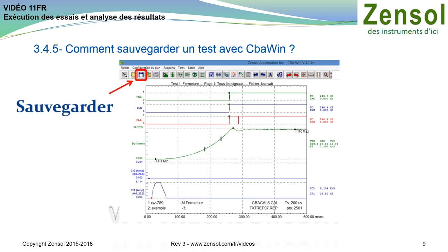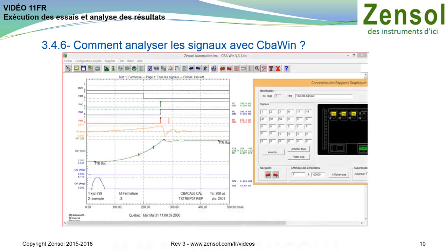As mentioned above, the red buttons are used to analyze the various signals. To zoom in on the curves, use horizontal and vertical expansion. To zoom in on the calculations on the right, use the loupe icon. This slide shows the travel of a KSO circuit breaker displacement signal, amplified in X and Y.